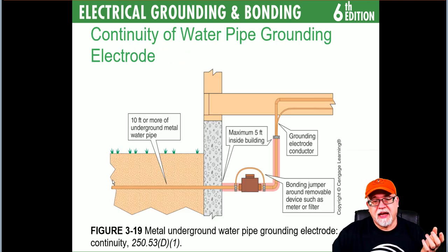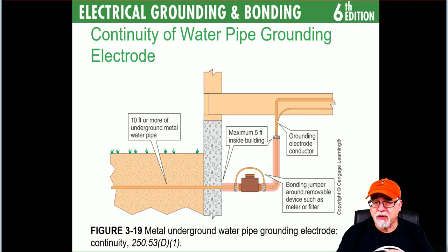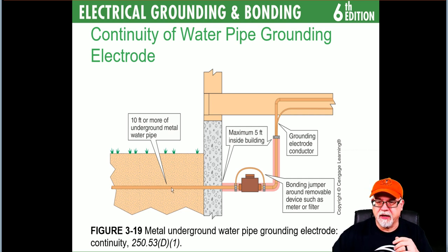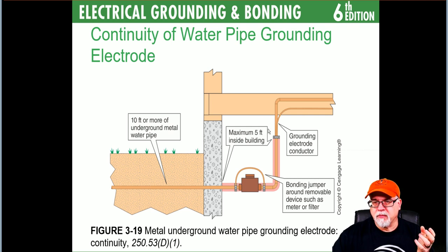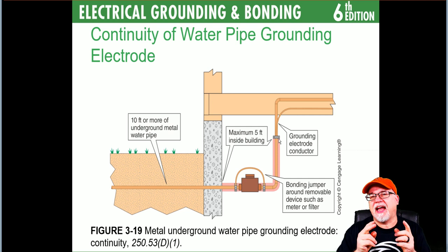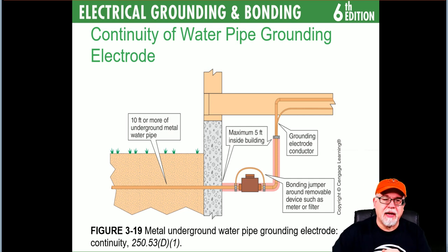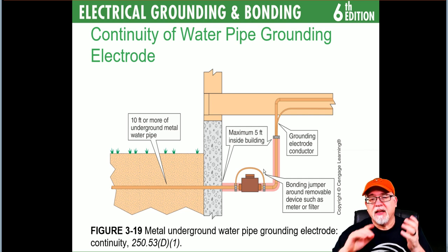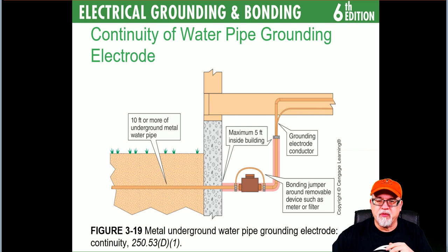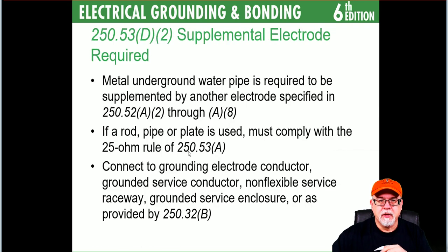Regarding continuity: if you have an underground water pipe ground and there's a water meter that can affect any connection on the load side, you have to bond over that water meter to maintain the integrity of the connection. If the meter is removable, that can break the path to the electrode downstream. You're making your connection within the five-foot point of entry — if a meter can be removed and affect that integrity, you put a jumper on it.